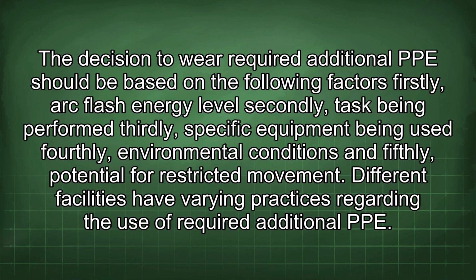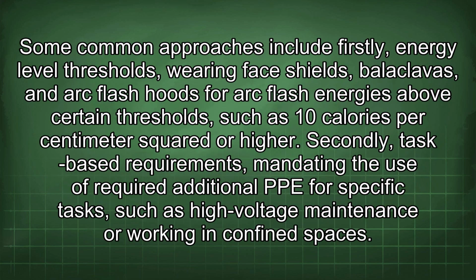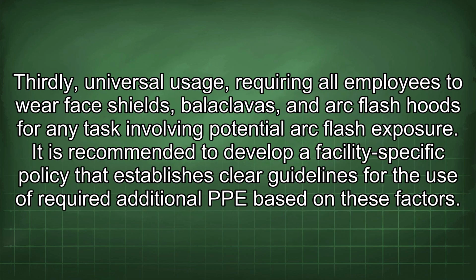Different facilities have varying practices regarding the use of required additional PPE. Some common approaches include: firstly, energy level thresholds, wearing face shields, balaclavas, and arc flash hoods for arc flash energies above certain thresholds such as 10 calories per centimeter squared or higher. Secondly, task-based requirements, mandating the use of required additional PPE for specific tasks such as high voltage maintenance or working in confined spaces. Thirdly, universal usage, requiring all employees to wear face shields, balaclavas, and arc flash hoods for any task involving potential arc flash exposure.